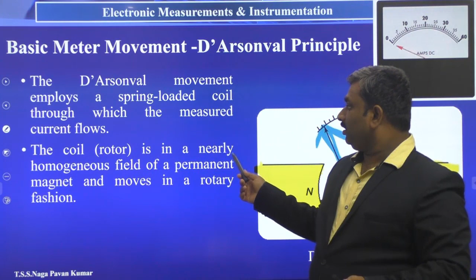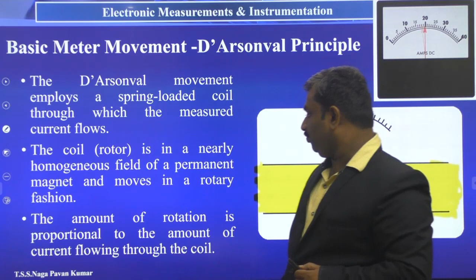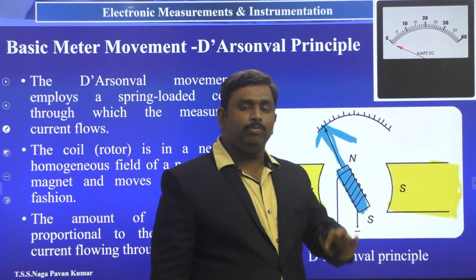So the coil or rotor is in a nearly homogeneous field of a permanent magnet and moves in a rotary fashion. So this rotor we have to place in between the magnetic field. That is the coil arrangement. The amount of rotation is proportional to the amount of current flowing through the coil. How much this conductor is moving is completely based on the flowing current through this coil. That is directly proportional to the movement of the conductor.